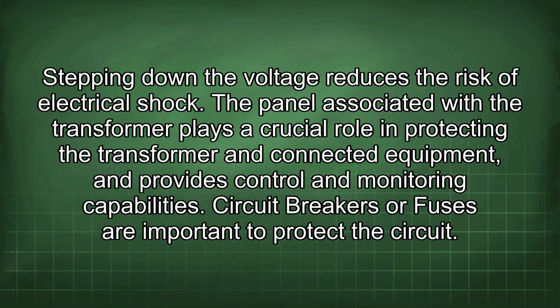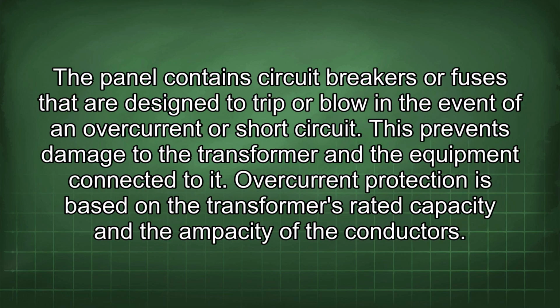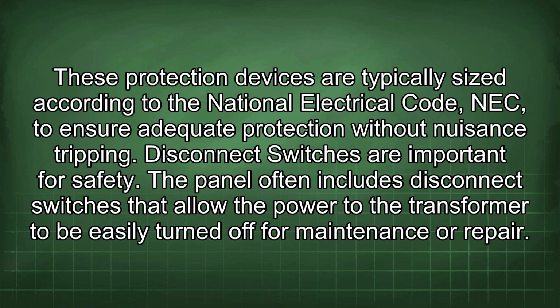The panel associated with the transformer plays a crucial role in protecting the transformer and connected equipment, and provides control and monitoring capabilities. Circuit breakers or fuses are important to protect the circuit. The panel contains circuit breakers or fuses that are designed to trip or blow in the event of an overcurrent or short circuit. This prevents damage to the transformer and the equipment connected to it. Overcurrent protection is based on the transformer's rated capacity and the ampacity of the conductors. These protection devices are typically sized according to the National Electrical Code (NEC) to ensure adequate protection without nuisance tripping.